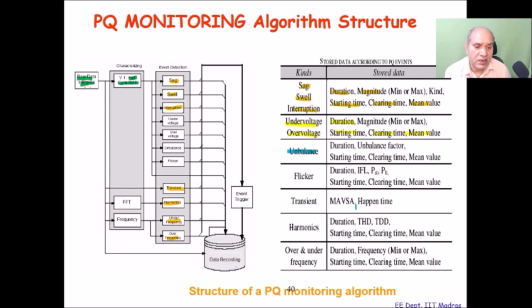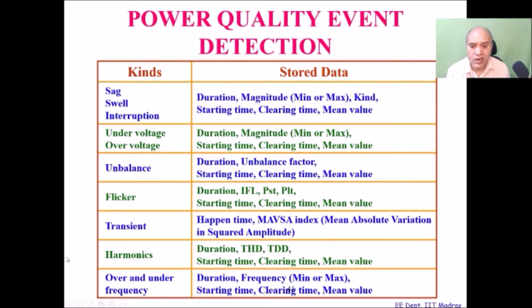In transient, there is MAVSA or happen time index. For harmonics, we have duration, THD and TDD, starting time, clearing time. For under and over frequency, there are duration and frequency, starting time and clearing time, frequency variations. They are explained more here, the correct meaning. So these are the important parameters that I mentioned, okay? Sags, swells, interruptions, under voltage, unbalance, flicker, transient, harmonics, over and under frequency. As I mentioned, mostly we will be measuring the magnitude and duration, then starting time and the clearing time, okay? Starting time and the clearing time and mean value of these.